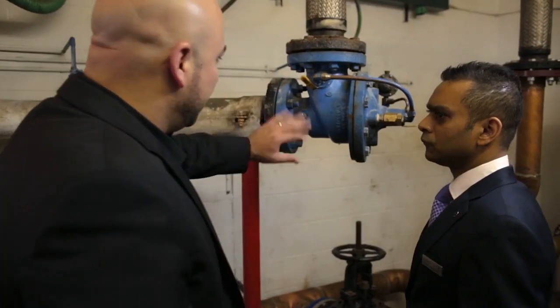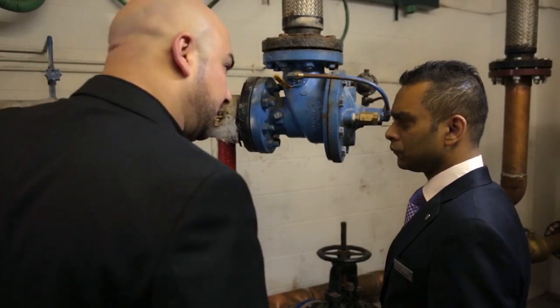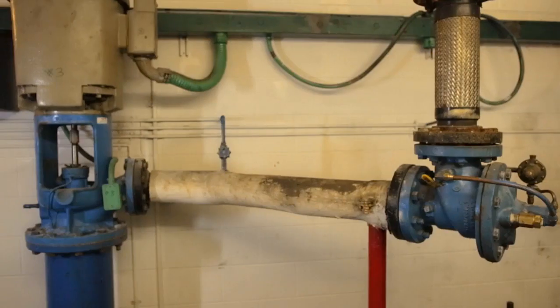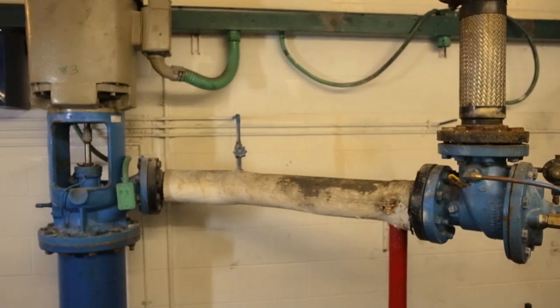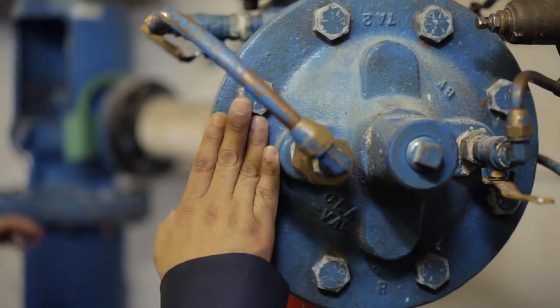The Pump Audit Program is a program developed by Grundfos for about 10 years now, and it is an innovation in the pump world. It is an excellent tool to enable us to not just find out the efficiency of the existing pump or pump system, it actually helps us redesign the system. When we look at pumps in general, we usually have problems in the design, and that causes the pump to be a little bit oversized, which causes the energy wastage.